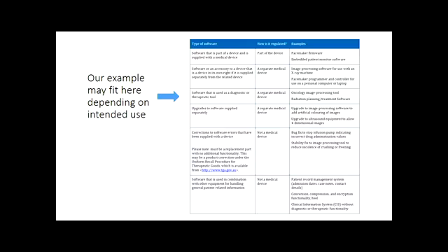And there's some examples there, but even upgrades to software that are supplied separately can be deemed to be a medical device as well. All right, so if you got a device and it had some sort of software error in it and you sent a software package to fix that error, do you think that would be a medical device or not? The software package itself? No.